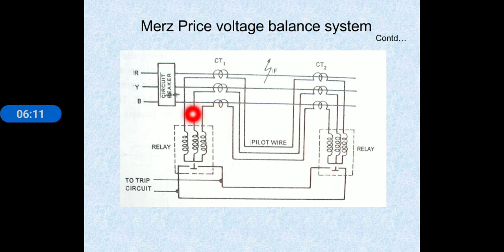In normal conditions, the entering current and leaving current of this phase are equal. At that time, voltages are also equal at both secondary ends of the current transformers. It means the same voltage is maintained at the secondary ends, so we can say the voltages are in balance. At that time, no current is allowed to flow through this relay.